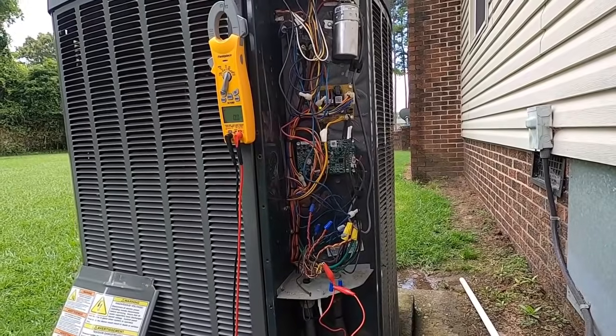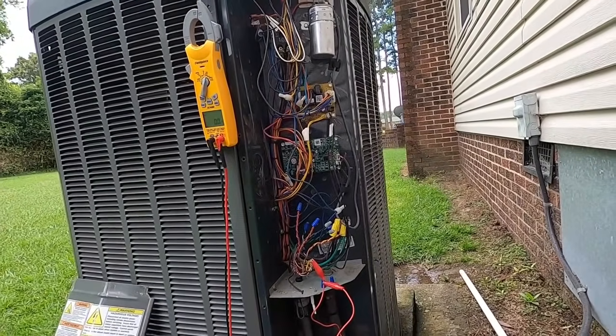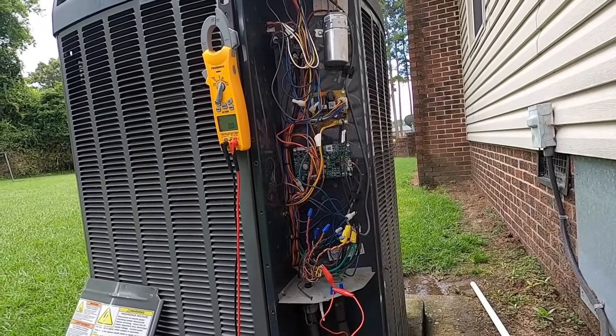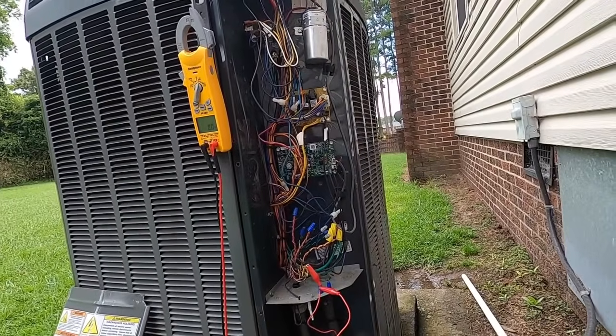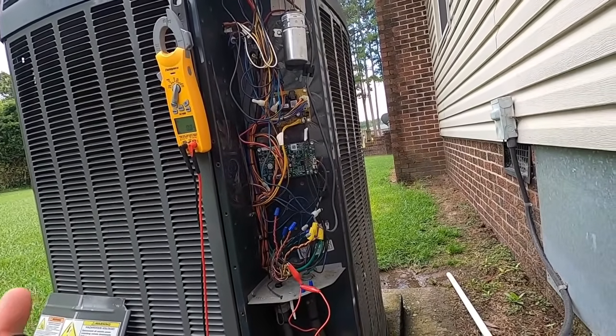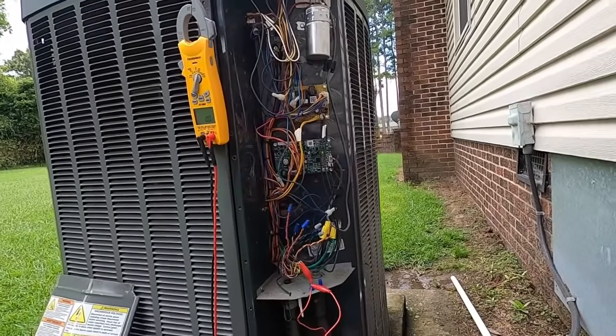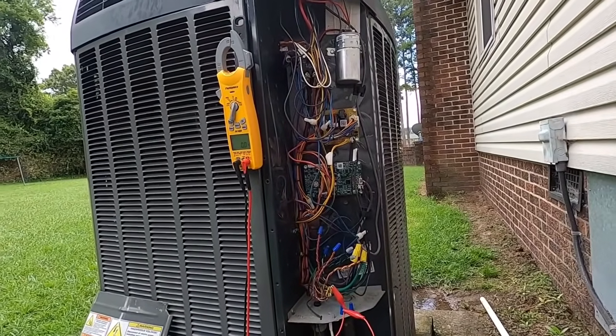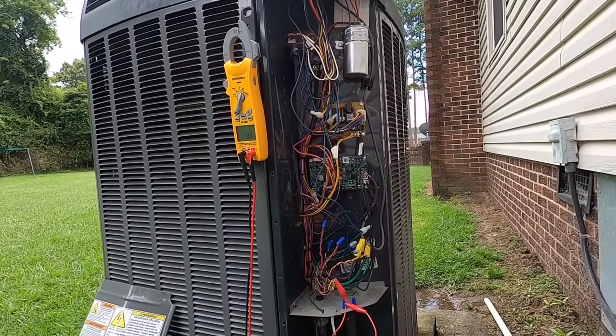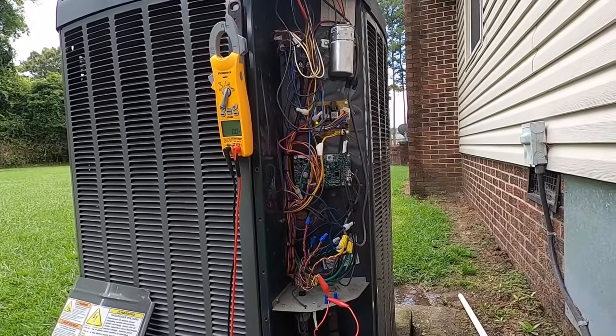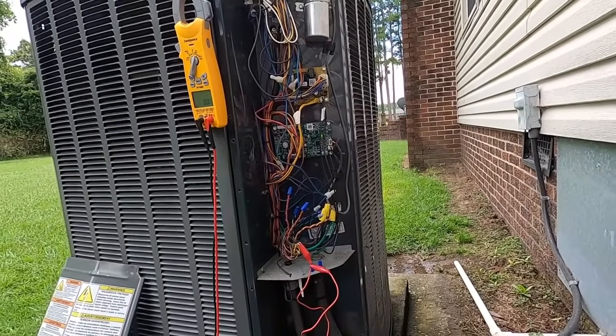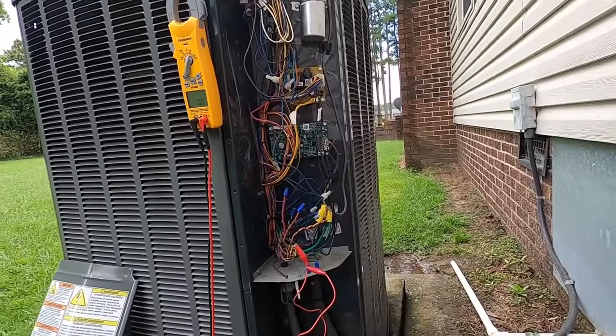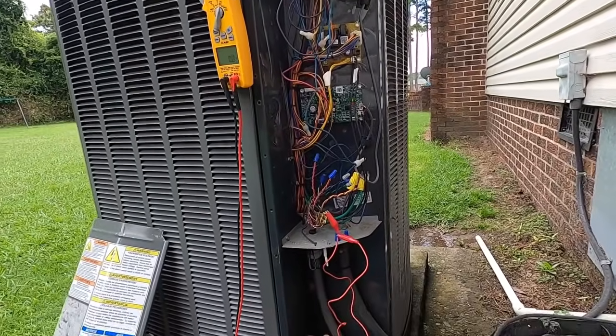And I did bring one out. We've got 2 training units set up at a shop. One's an XV, one is a 2-stage 18i with a TAM 8 air handler on it, which is I believe what's on this. I did bring that board out of that unit with me just in case, as a temporary band-aid until we can get the new one in. Still under warranty. It's 2015 under parts warranty.